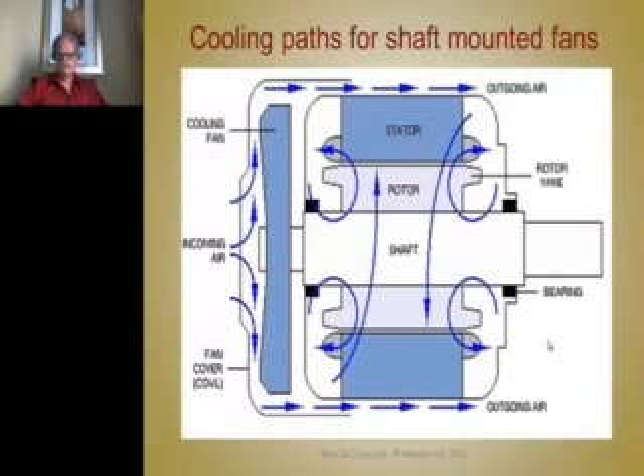Here's a cross-section of a simple induction motor with an external fan. This is typical of many machines, and the way this is cooled, this is a totally enclosed motor here with a frame around it, and the stator's in there. The rotor's mounted on the shaft, there's bearings in here, and maybe seals, maybe not.